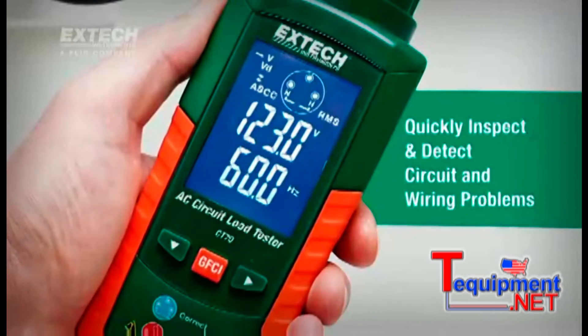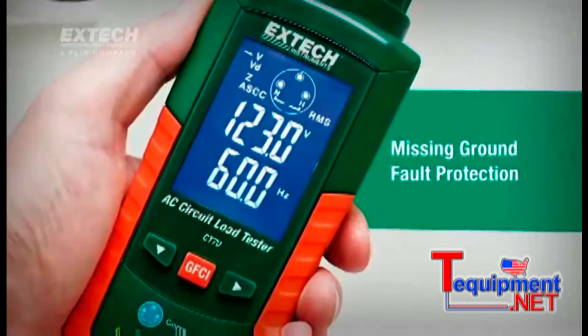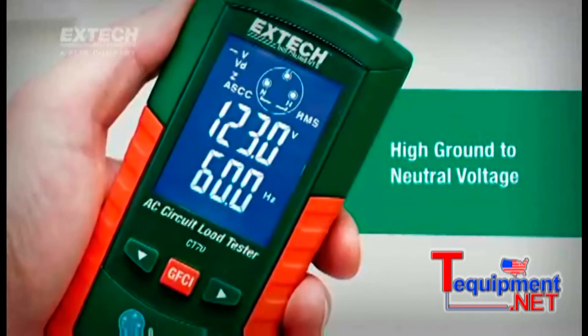The Extech CT70 quickly inspects and detects circuit and wiring problems such as poor ground impedance, false grounds, missing ground fault protection, low voltage availability under load, and high ground to neutral voltage.